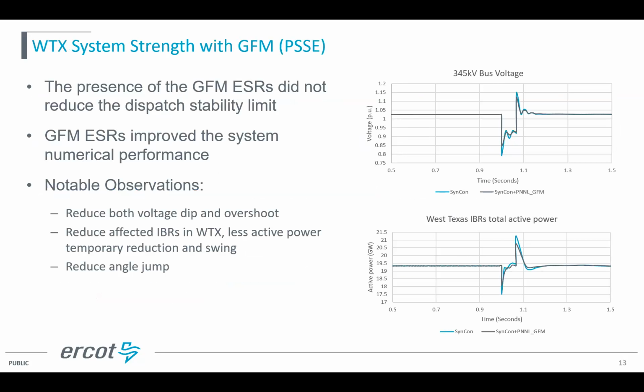Here are some simulation results. First, adding grid forming did not reduce the stability limit. Of course, it probably will increase the stability limit, but that is not our study focus. We also found that grid-forming batteries improve the system numerical performance, because in the past we often saw PSSE crash. After we plug in the grid-forming battery models, that problem doesn't go away, but it improves significantly. We also have a few notable observations: it reduces the voltage dip and overshoot, reduces the active power reduction and the power swing, and reduces the angle jump.